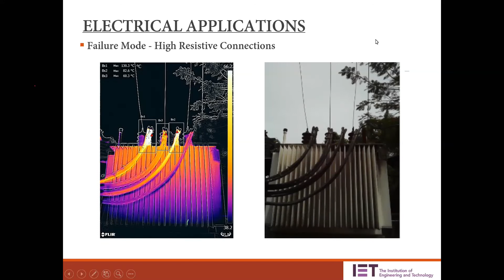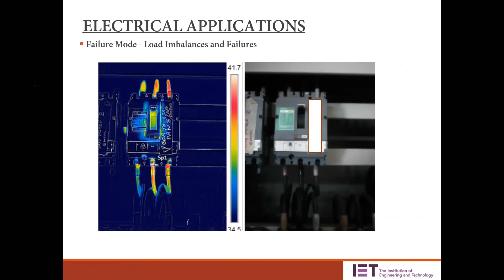And there can be load balance problems, load failure, and improper balance, which is a very common issue in the industrial environment. So you can see the phase here is the hottest, and this is comparatively colder, which says that the three phases are not equally loaded. And we have seen cases where one particular phase is very cold, which says that the phase has failed. It's a possibility. So using other instruments, you can check the voltages and currents through the phases to pinpoint what the issue is.